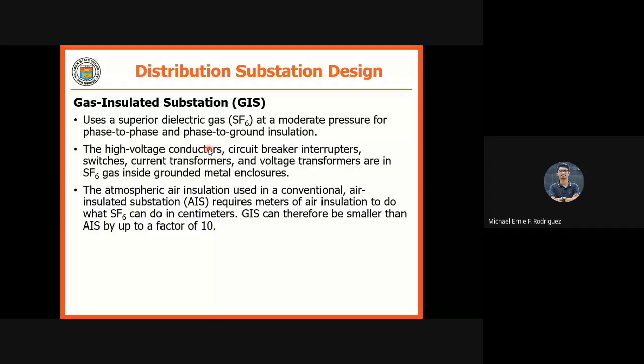In short, the atmospheric air insulation is used in a conventional AIS substation. A conventional substation, or AIS, requires meters of air insulation. Okay? With SF6, it is only centimeters. Compare that. With AIS, meters are needed for phase-to-phase or phase-to-ground clearances, but with SF6, only centimeters. So your equipment can be placed close together, since you have SF6 gas as insulation. As a result, again, the GIS can be smaller than the AIS by a factor of up to 10.